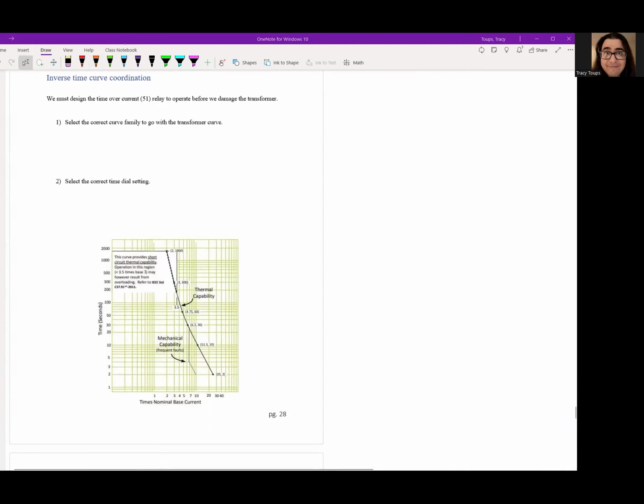So first off, select the correct curve family to go with the transformer. Remember, we have to choose the best fit curve. I remember you have that inverse, right? Very inverse, extremely inverse, right? There's a family of curves that will mimic the same kind of slope that this transformer has. And that's why they have different types of curves with different transformers, different equipment. So we might end up picking maybe a very inverse curve.